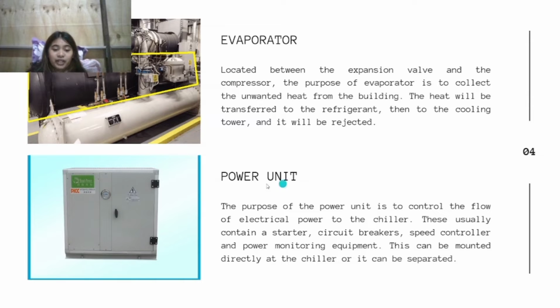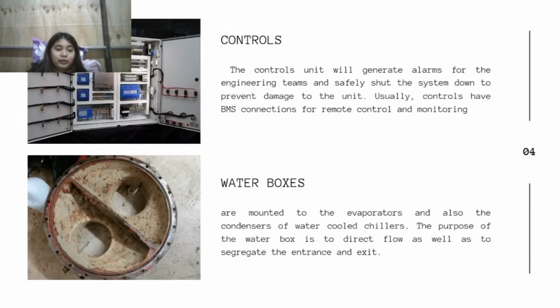So this is the power unit. The purpose of the power unit is to control the flow of electrical power to the chiller. Inside of a power unit there are controls. The control unit will generate alarms for the engineering teams and safely shut the system down to prevent damage to the unit. Usually, controls have BMS connections for remote control and monitoring.